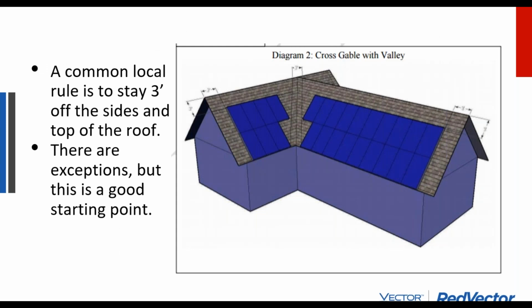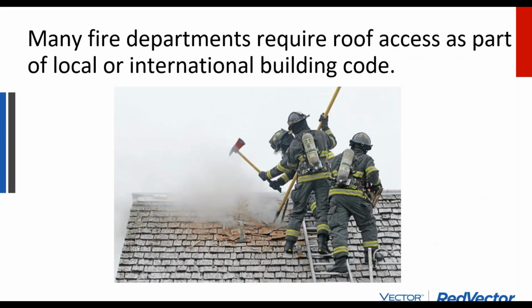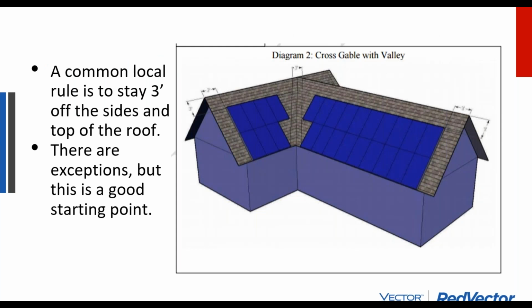And so in building code, not National Electric Code, in International Residential Code, International Building Code, California Fire Code, they say you have to stay basically 3 feet off the sides, 3 feet off the top of the roof with your solar array for firemen access to cut their holes in the top of the rooftop. So 3 feet off the sides, 3 feet off the top is the general rule of thumb. Not all jurisdictions abide by this. Some jurisdictions intentionally do not abide by this because they say in our jurisdiction, there's no fireman getting up on any roof to do this hole cutting stuff. So you can go wherever you want with it.